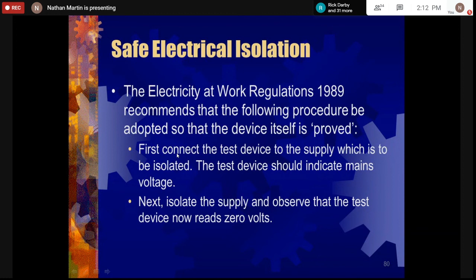But a lot of the time we just go and test the circuit, isolate the circuit, test again and it's dead, and that's it. But the proper testing procedure says you are to retest the device. Why? The device can become defective while you're testing. It can be a case that the voltage leaked the device, or that the device battery is low.